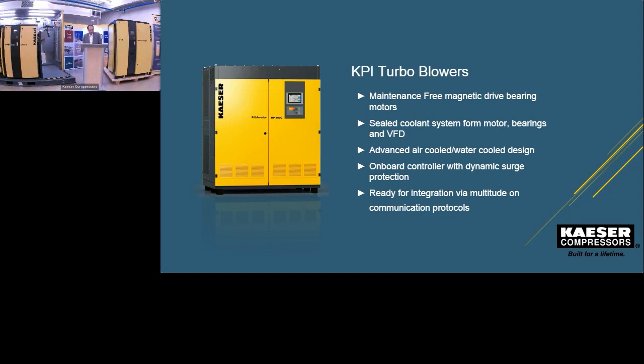So that's something new that's also on this machine. Now, as I mentioned before, it has a complete sealed cooling system, and that cooling system has an air-to-air heat exchanger as well as a water-to-water heat exchanger to remove the heat from the system. The air-to-air is a factory default. We also have this water-to-water, which is a nice solution.